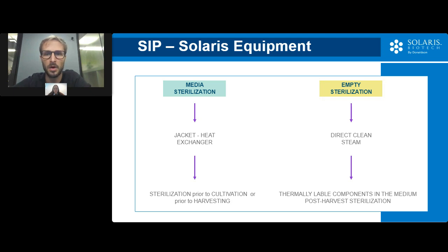The Solaris system offers flexible recipe configuration. This is true, of course, also for the sterilization phases. It is possible to operate based on time and temperature or the equivalent time, so F0. The software grants control over the main sterilization variables and on the PID parameters. It is possible to automatically monitor both the vessel and the peripheral lines sterilization through counters associated with temperature probes.